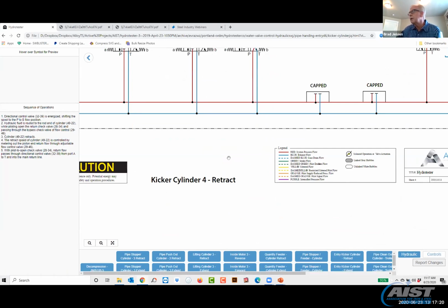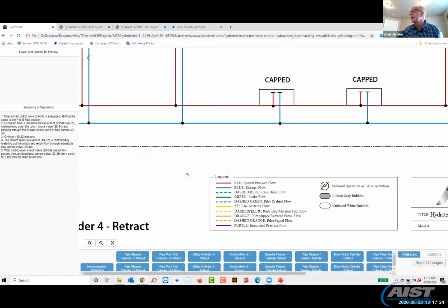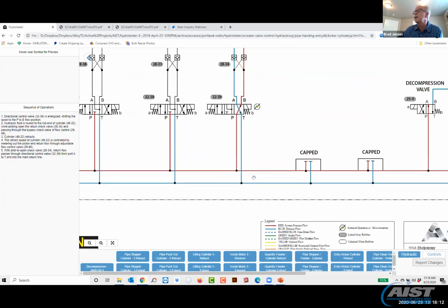And we have over here a legend that tells us that the red is system pressure, blue is exhaust flow, we've got case drain, yellow is metered flow, we've got orange, which is reduced pressure. These are all ISO industry standards. So if you were looking at, I know some OEMs such as Caterpillar are very good at showing you the different ISO color layers in their schematics so that you know what the condition of the fluid in the circuit is at any given time.